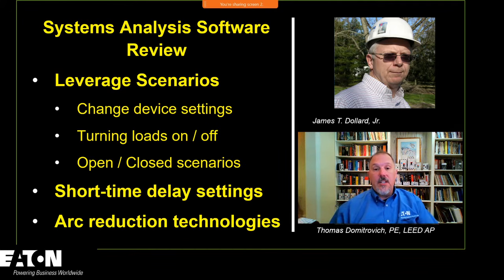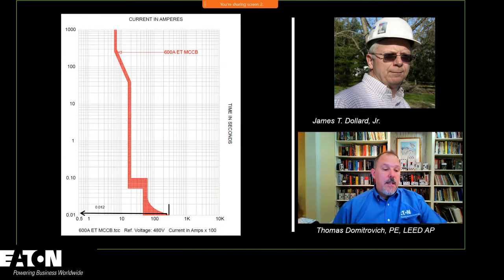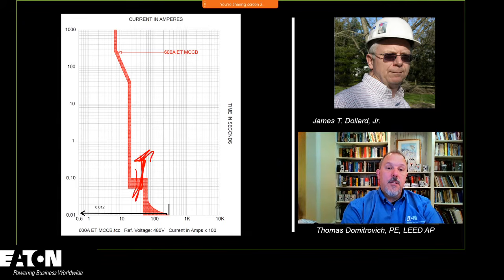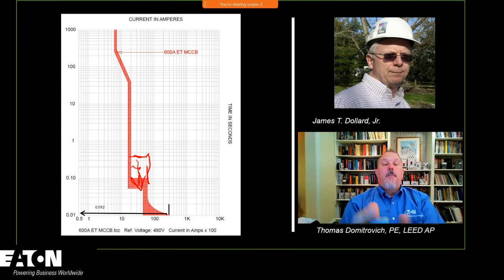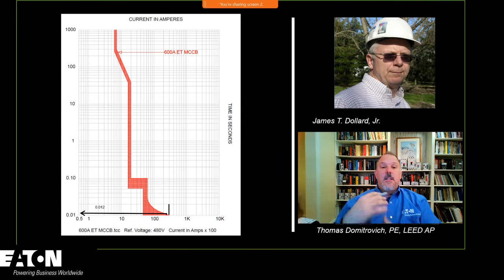You may be able to change some of your settings. If you look at this device here, where you have a trip curve with an electronic trip unit on it, you could possibly move this short time delay up and down. You may have it set, unfortunately, up here for no apparent reason, and if you can lower that set point, you can possibly lower your incident energy in your facility.